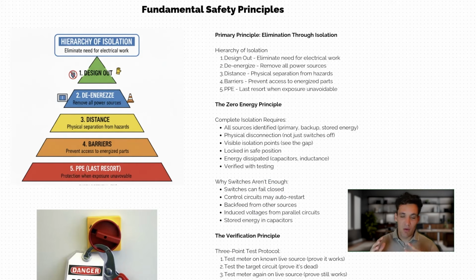So for example, if you have a capacitor bank or something like that, it's actually earthed and the electricity from it is dissipated. Because on large circuits, particularly really, really long cables, even if the power is disconnected, a long cable between a cable core and the screen can act as a capacitor and actually store charge. So when someone comes along and touches it, they'll get a shock. And on top of all these controls, before anyone does any work on anything, they actually test it to make sure that there's 0 volts.